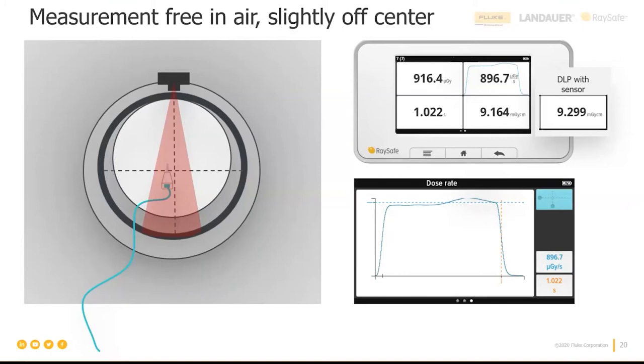If you've been lucky enough to save the waveform from your previous measurements and the numbers deviate from each other, you can use the waveform to check whether your measurements were accurate at that time or not. If your positioning was accurate and the numbers still deviate, then you have a deviation. But if you can see that the waveform wasn't perfect, then that might be the reason for your deviation in measurement and not the output from the machine itself.